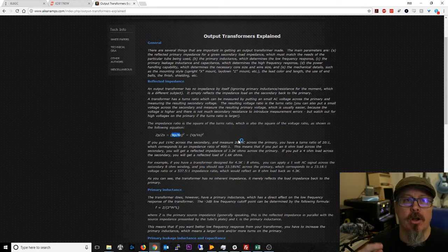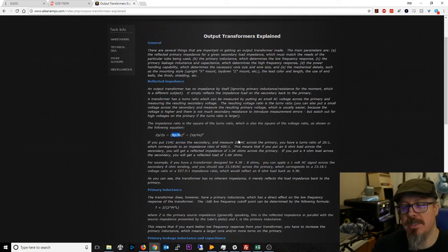So they won't arc and cause damage or blow up the transformer or kill you. But you connect those to the multimeter, separate those leads apart, and then put that 10 volts in, or 1 volt, or whatever you might want to see. You will then get an opposing end voltage that gives you that voltage rating, which is also basically the equivalent of the turns ratio. So say you put in 10 volts, the output was 200 volts. That meant that's a 20 to 1, or 200 divided by 10, turns ratio slash voltage ratio.